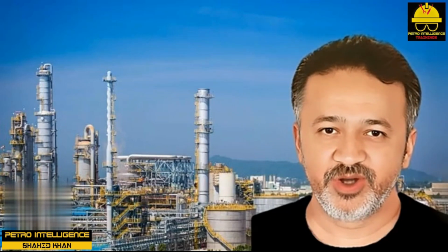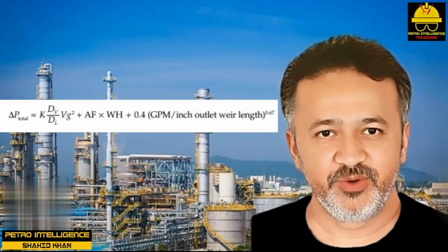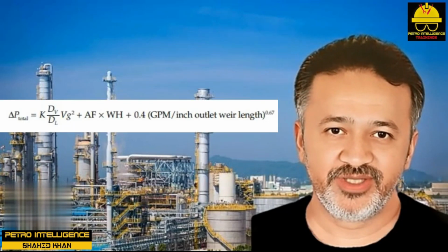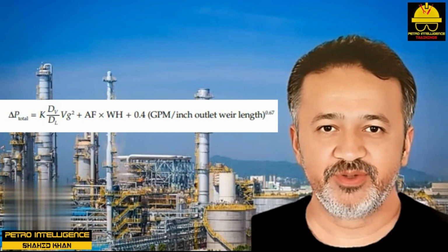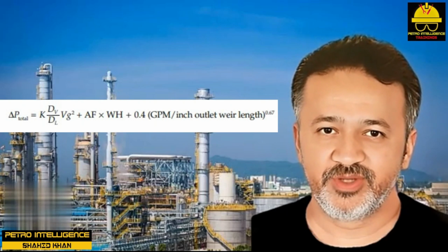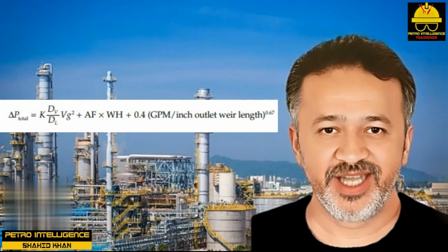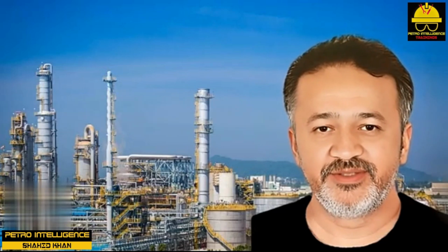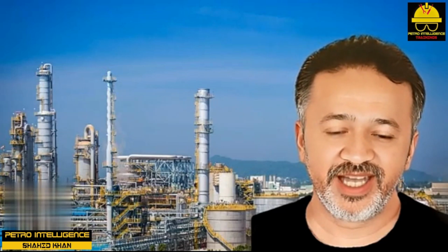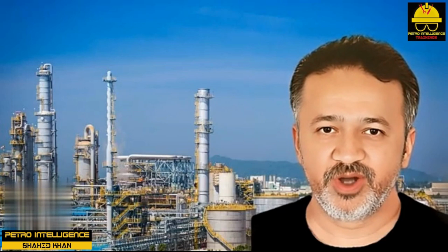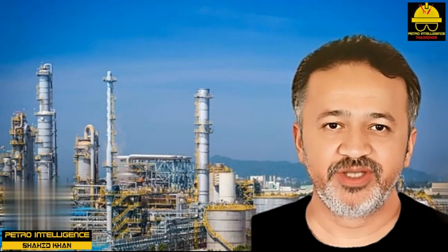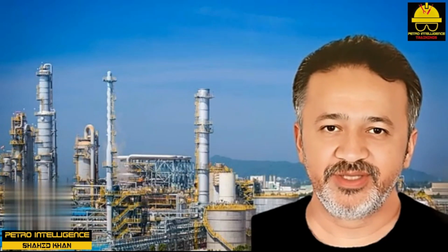While various valve tray vendors maintain that this rule does not hold for their equipment, it is the industrial experience that valve trays leak just as badly as do sieve trays at low vapor hole velocities. To summarize, increment P total equals K times Dv divided by DL times Vg squared plus AF times WH plus 0.4 GPM per inch outlet weir length, caret 0.67.